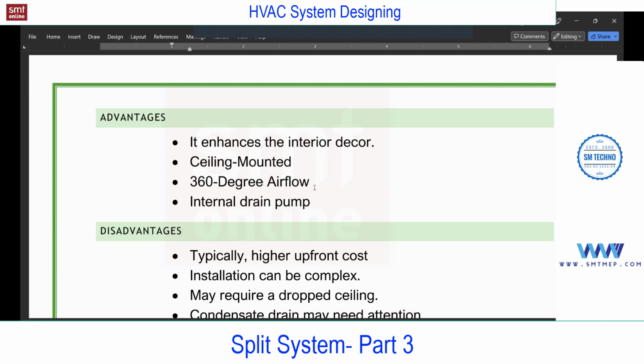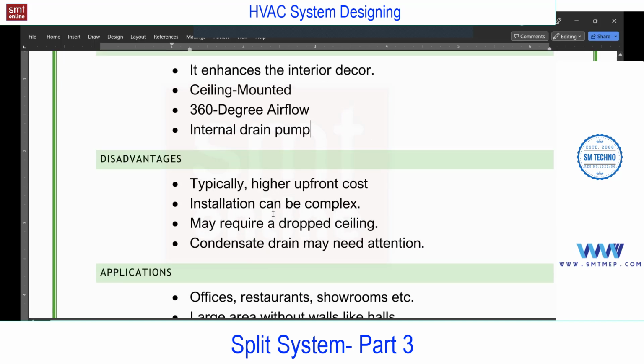And for air distribution point of view also, you can expect the uniform distribution of air compared with the high wall. And it's a ceiling suspended, and the unit is not visible in the space except that panel. Only the panel is visible. The complete unit is concealed. But in case of high wall, the complete indoor unit, this FCU, is visible. Next, internal drain pump, what we discussed just now. Disadvantage, cost. You see the cost is higher compared with the high wall for the same capacity.